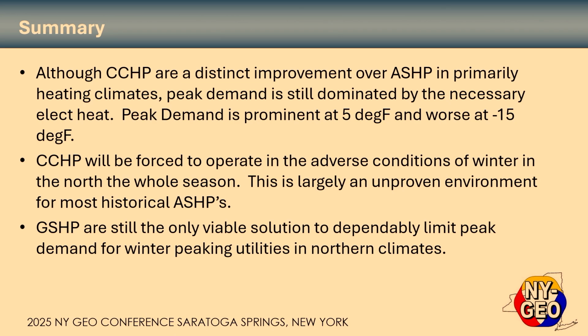And I can't say this enough, I don't know that we've got a lot of cold weather experience with air source heat pumps, because most of them have been shut off at 37. And so when it gets really cold out, I don't know that we have a ton of experience as to how they're going to react to that. And we're embarking now with making a lot of air source heat pumps work very hard at those cold temperatures and go in and out of defrost and that sort of thing.